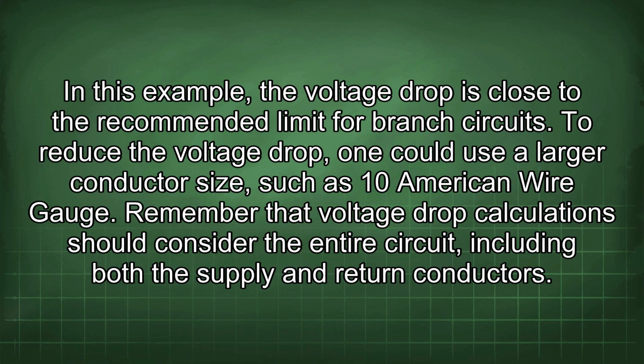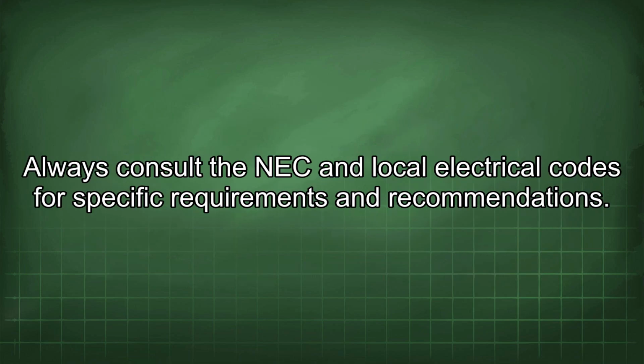In this example, the voltage drop is close to the recommended limit for branch circuits. To reduce the voltage drop, one could use a larger conductor size, such as 10 American wire gauge. Remember that voltage drop calculations should consider the entire circuit, including both the supply and return conductors. Always consult the NEC and local electrical codes for specific requirements and recommendations.